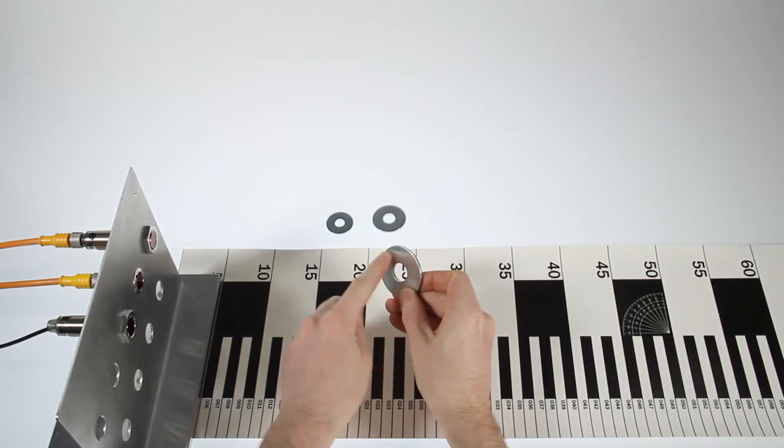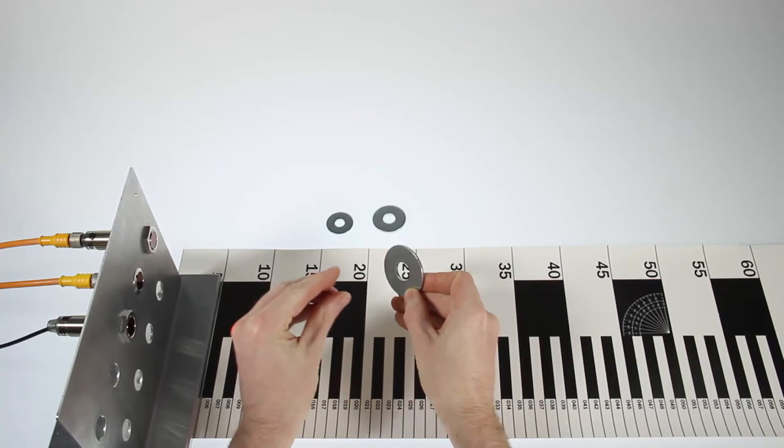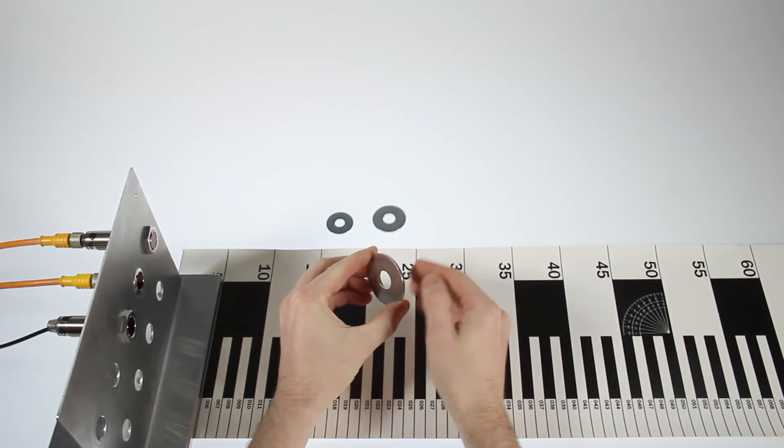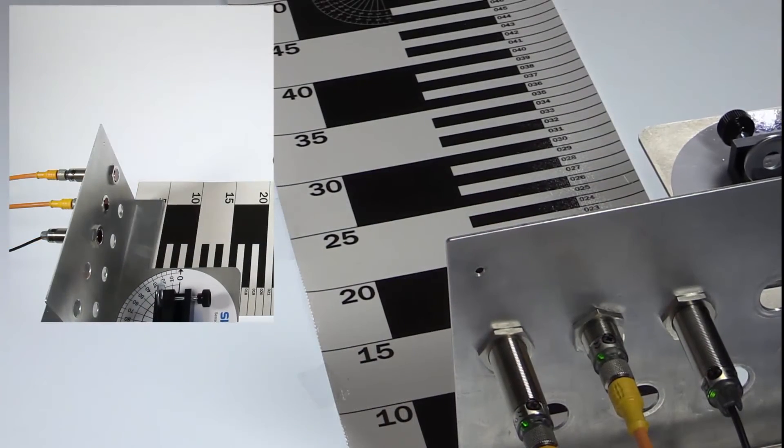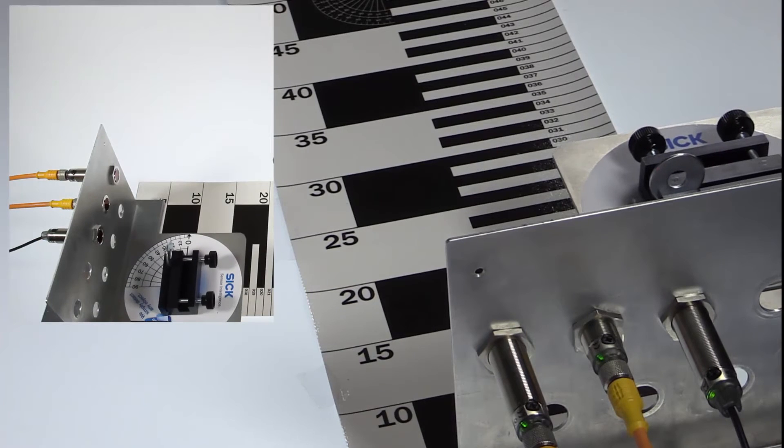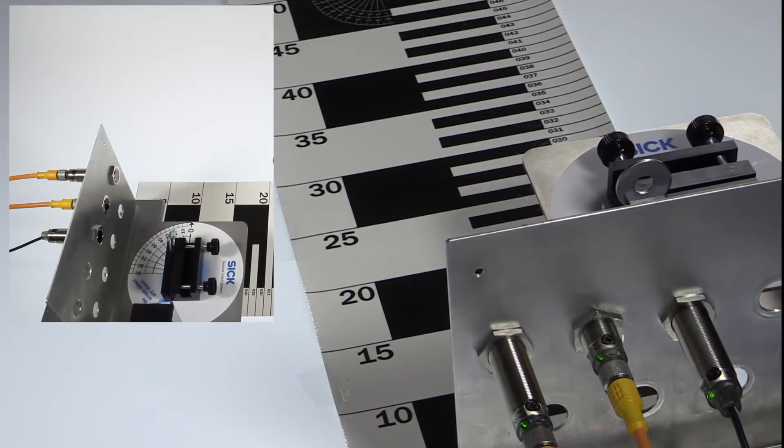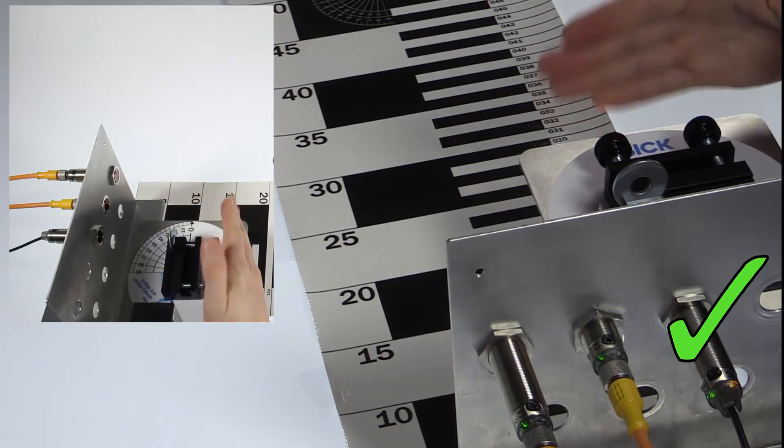An example would be having a cutout on some machine part. The sensor is mounted behind the surface and detects the objects through the cutout. This will work, depending on the hole size, quite good for the background suppression version and the 400mm energetic version using the Pinpoint LED.